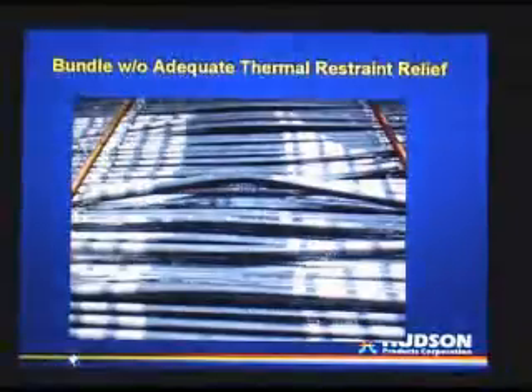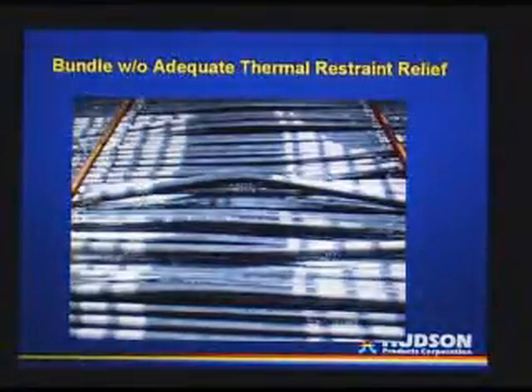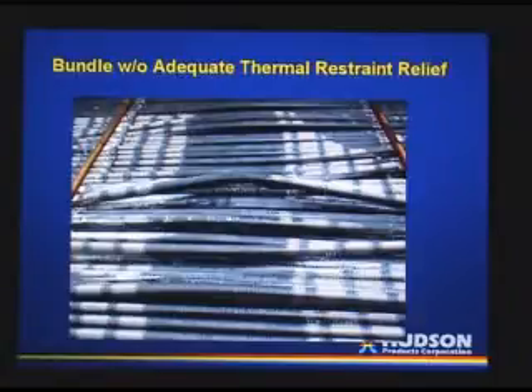If you restrict it, you're basically forcing the top tubes to deform so that they can account for the thermal expansion between adjacent tubes, between different tube rows.